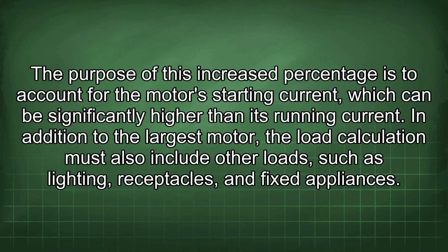The purpose of this increased percentage is to account for the motor's starting current, which can be significantly higher than its running current. In addition to the largest motor, the load calculation must also include other loads such as lighting, receptacles, and fixed appliances.